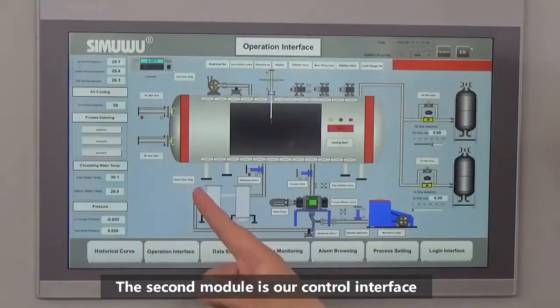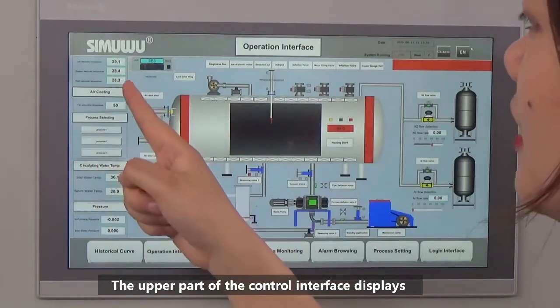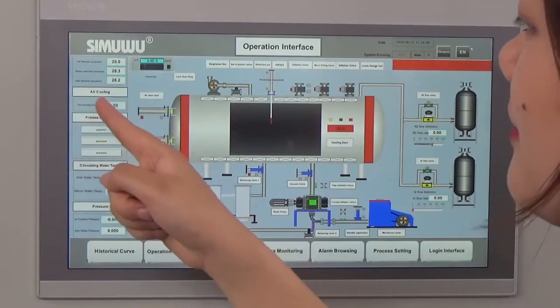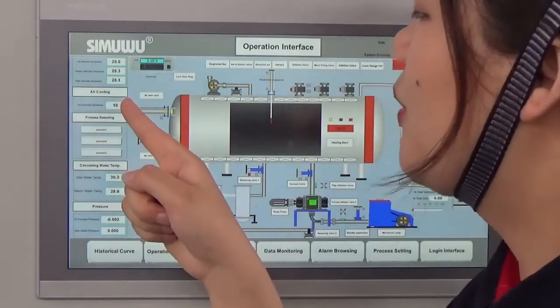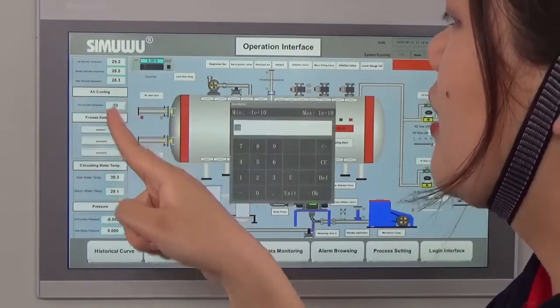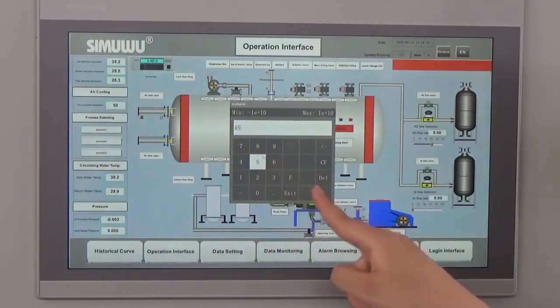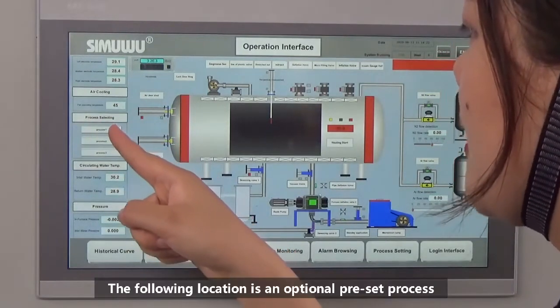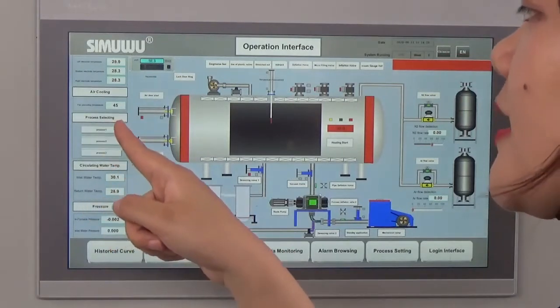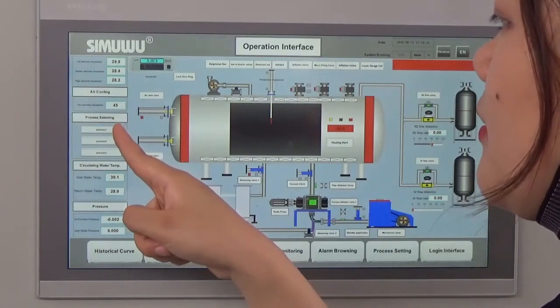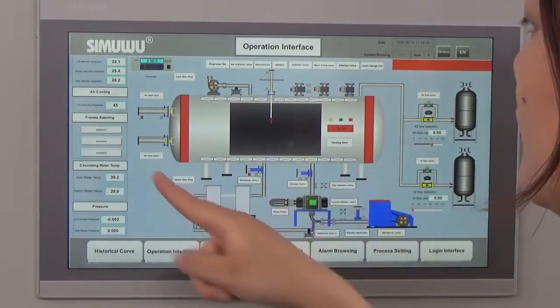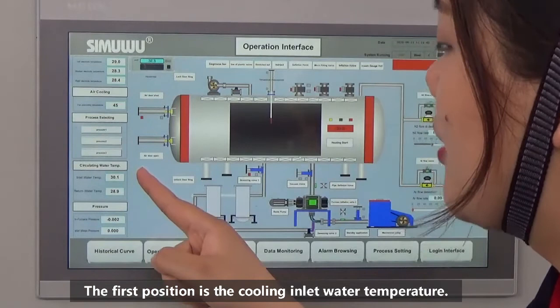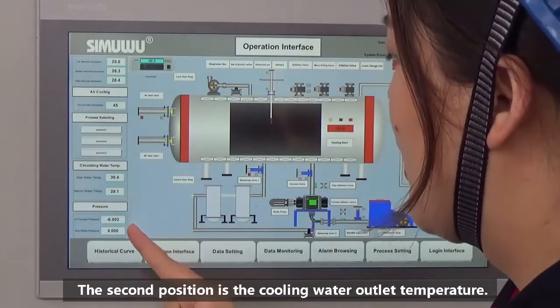The second module is our control interface. The upper part displays the real-time temperature of the 3 water-cooled electrodes. Below is the lowest furnace temperature. You can set the door-open temperature here — only when that temperature is reached can the furnace door be opened. The following location shows an optional preset process, which we will discuss later. The following position shows the cooling water temperature: the first is the cooling inlet water temperature and the second is the cooling water outlet temperature.